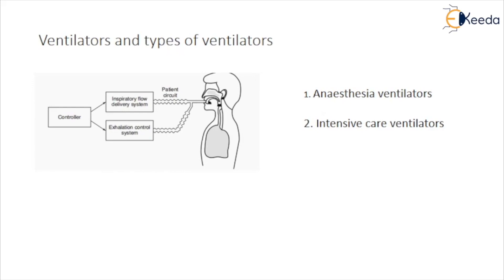Positive pressure ventilators generate respiratory flow by applying positive pressure — greater than atmospheric pressure — to the airways. During inspiration, the inspiratory flow delivery system creates positive pressure in the patient circuit while the exhalation control system closes the outlet to the atmosphere. There are two types of ventilators: anesthesia ventilators, which are generally small and simple equipment used to give regular assisted breathing during an operation; and intensive care ventilators, which are more complicated, give accurate control over a wider range of parameters, and often incorporate a patient triggering facility — delivering air to the patient when the patient tries to inhale.